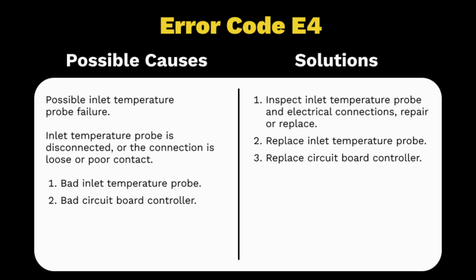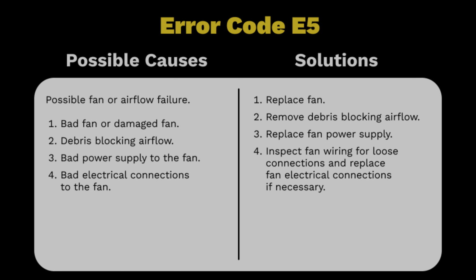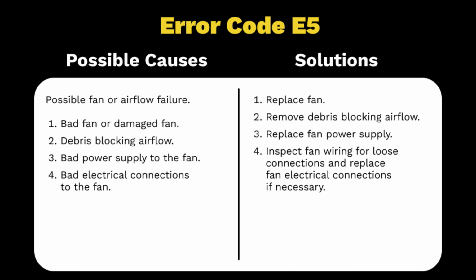If an error code E4 presents, this points to a possible failure of the inlet temperature probe. Check the probe and its electrical connections, repair or replace as needed. If an error code E5 presents, this indicates a possible fan or airflow failure. If the fan is damaged or not working, replace it or check it for cleanliness.